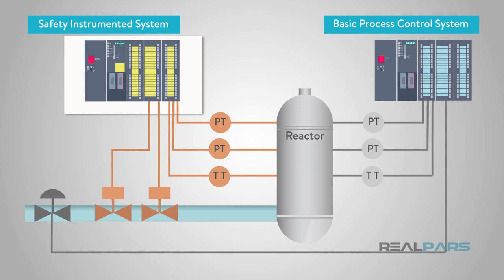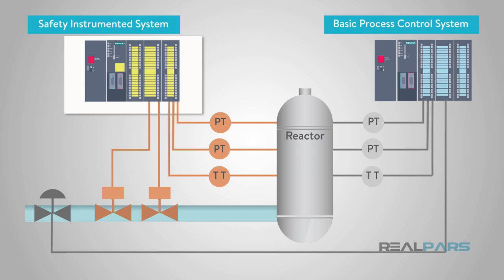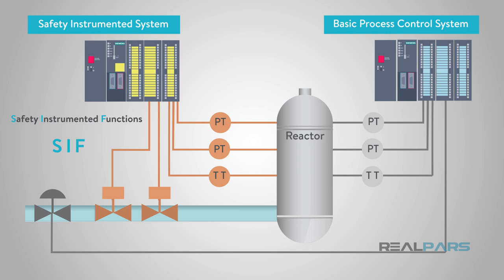The logic solver is a specialized hardened PLC-like device that may have multiple processors executing the logic in parallel to ensure integrity of the logic and resulting action. The SIS is designed around individual functions in the plant called Safety Instrumented Functions, or SIF for short. The logic solver takes the SIS inputs and determines what the state of the SIS outputs should be for that SIF.